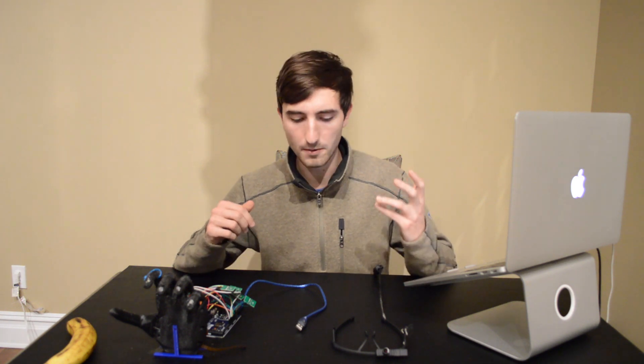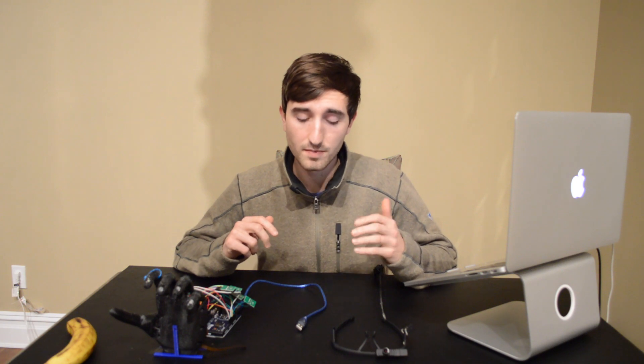So we have these super complex devices that have 20 to 30 grasp types available, but users are really only using two to three grasps because it's just simply too difficult to control. The way they're currently controlled is something called myoelectric control, which essentially just maps combinations of isolated muscle contractions to motions of the prosthetic hand. So one example that resonates with me is trying to flex my bicep without flexing my tricep, which if you try, it's actually quite difficult.